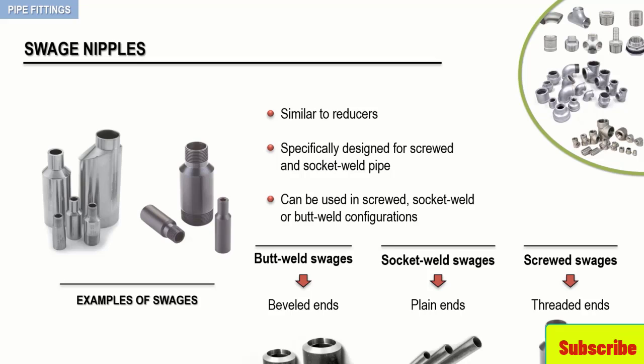Because socket weld swages are inserted into mating fittings, many companies allow the substitution of beveled end swages. Since the end is inserted into the fitting and the weld is made on the outside of the fitting, it makes little difference how the end cut is made.